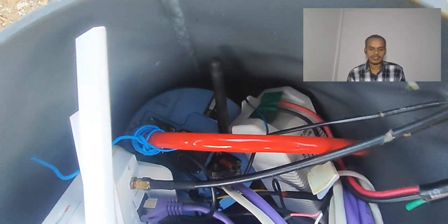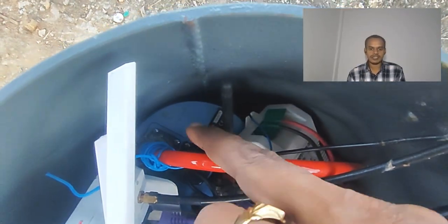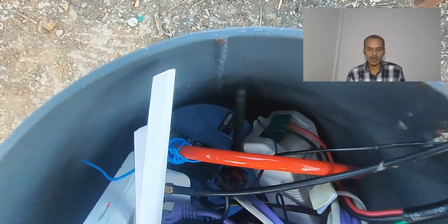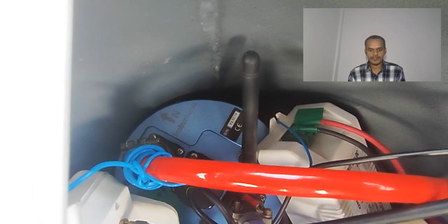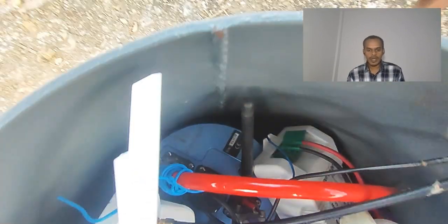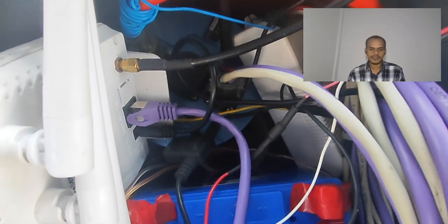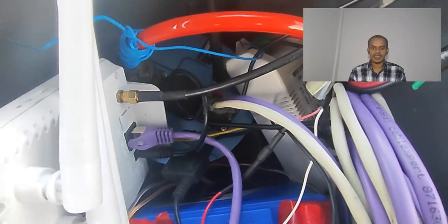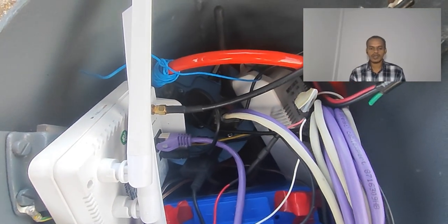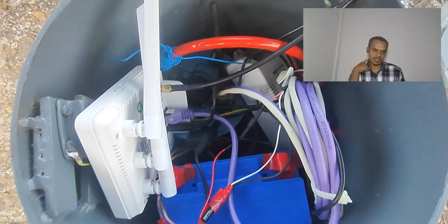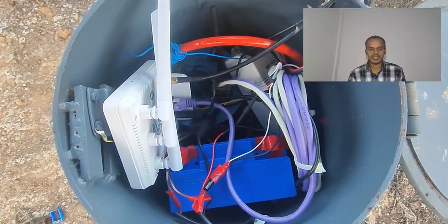And here you can see the digitizer in which the data will be recorded, and this is particularly faced in the north direction. I'll tell you why we have to install the instrument facing north in the coming videos. So this is how a setup will look, and this is the installation part. It looks messy, but this is how it looks. You can also go for wider containers in which you can keep everything neatly.